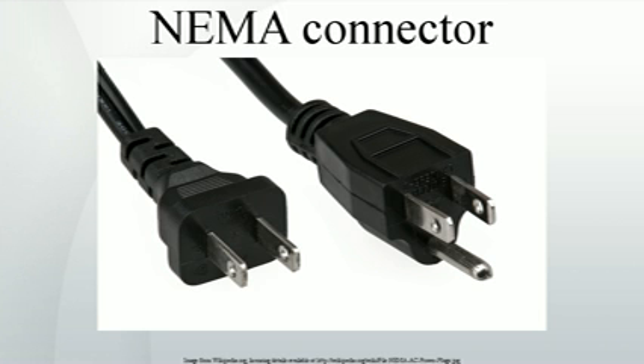Since North American dryers and ranges have certain parts, timers, lights, fans, etc. that run on 120V, this means that the wire used for grounding is also carrying current. Although this is contrary to modern grounding practice, such installations remain common in the United States and are relatively safe, because the larger conductors used are less likely to be broken than the smaller conductors used in ordinary appliance cords, and the current carried on the neutral conductor is small. NEMA 10-20 devices are very rare nowadays, but are occasionally found in homes that once had a large window air conditioner.